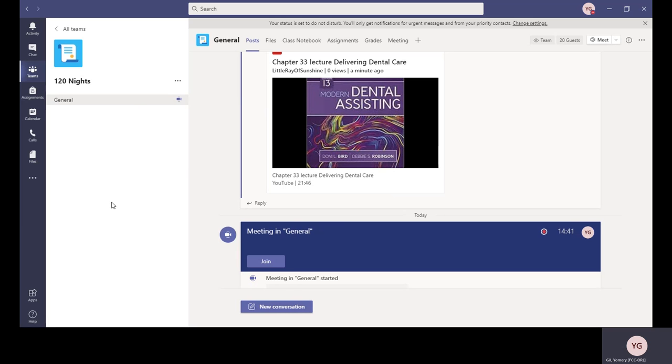Sterilization procedure sheets. Sterilization instructions vary not only between manufacturers, but also between different models made by the same manufacturer. So use of a sterilization procedure sheet is one way to avoid errors in handpiece sterilization. Exactly what I was saying, not all handpieces are sterilized the same way, so when you get into the office, they will let you know how they want you to sterilize these handpieces.